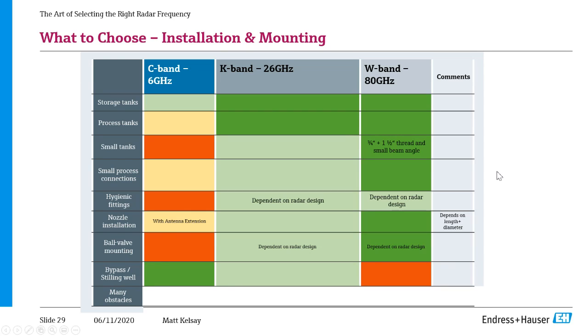Installation in a bypass or stilling well. Talked about this, lower frequencies are going to be better here, but the best is actually a guided wave radar. And with many obstacles in your tank, you're going to be better off with a high frequency radar, and that's just due to the fact that you've got a smaller beam angle, which means less commissioning work for you.